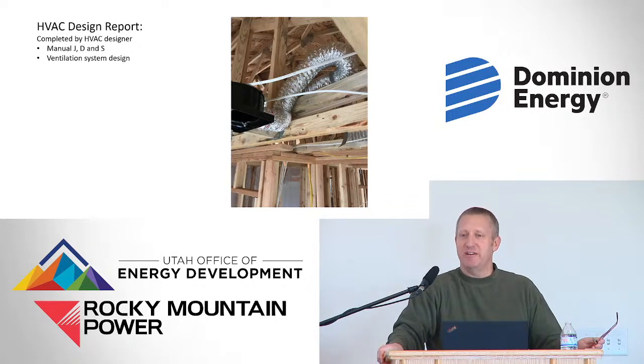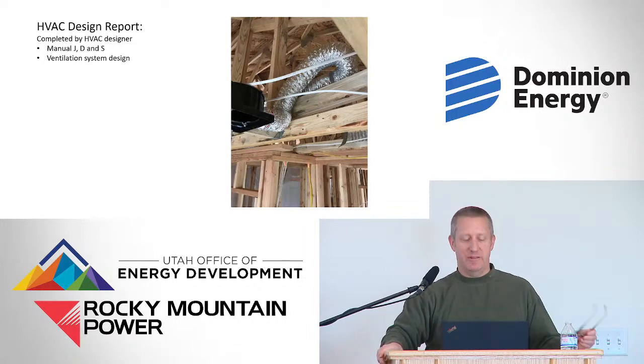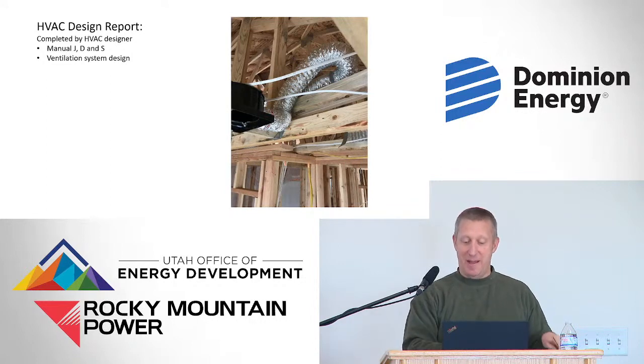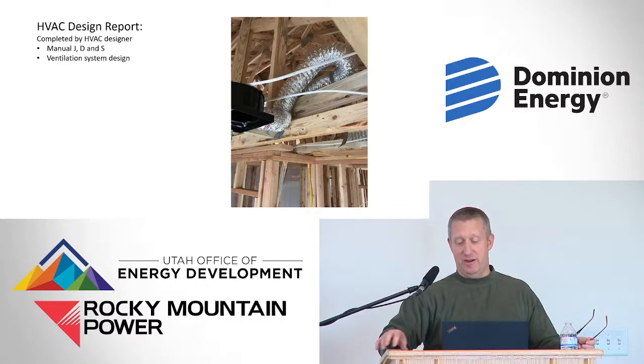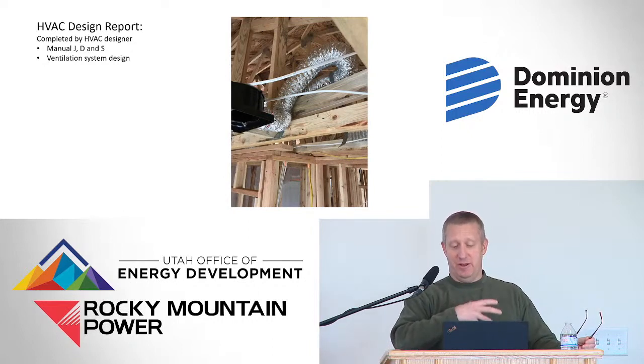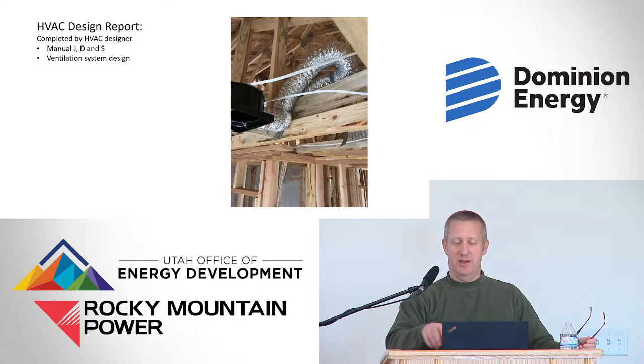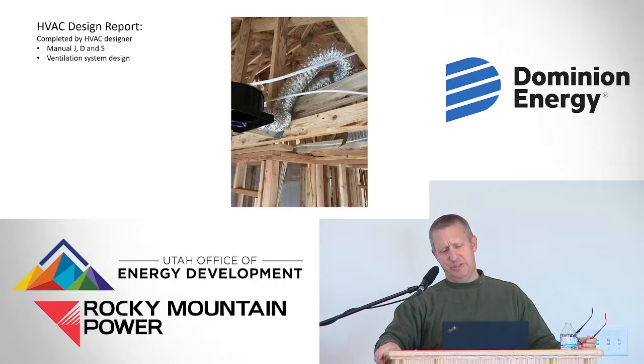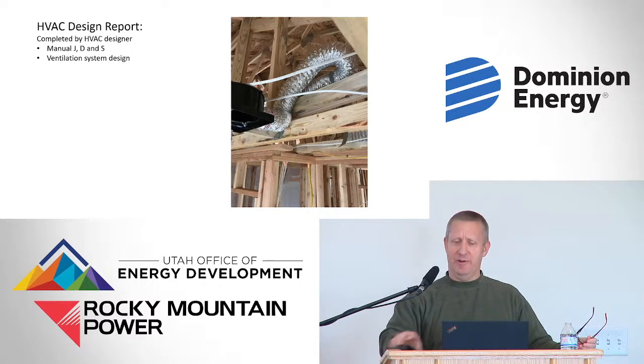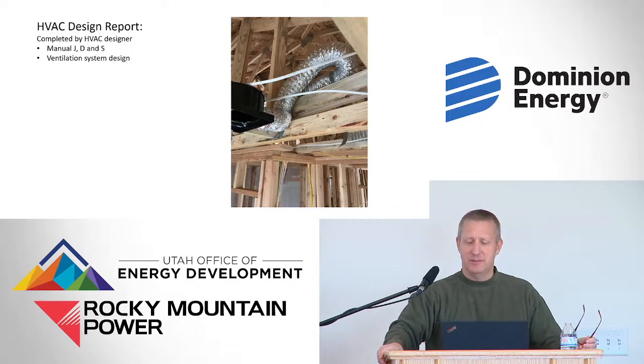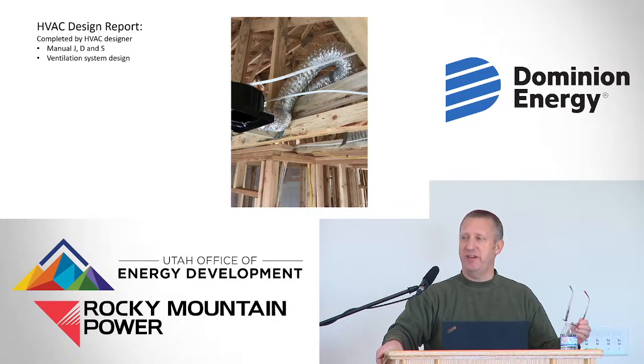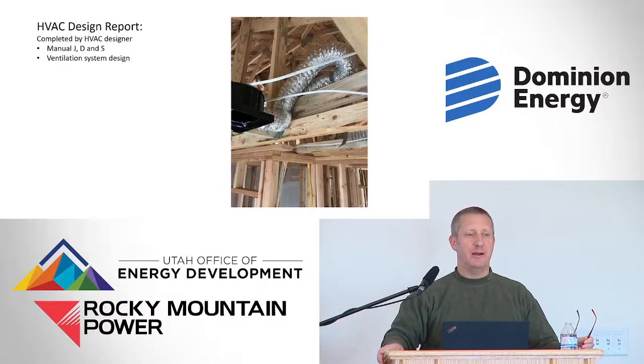But it's probably moving, I'm spitballing here, 25 CFM because of the way that duct is installed. Fans in furnaces and ventilation systems aren't designed to push very much pressure, and having it come right out of the fan into a truss with a hard corner significantly diminishes the amount of air it will move. Then putting close to a 180 degree loop in it is the equivalent of probably 50 to 60 feet of straight pipe.